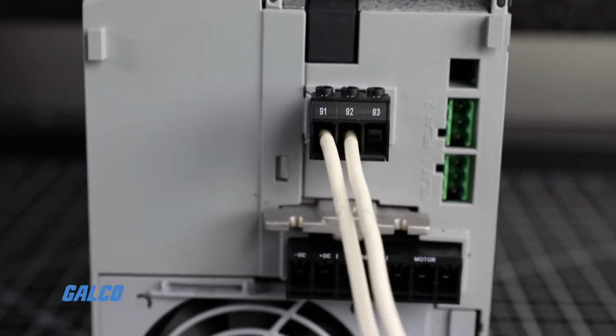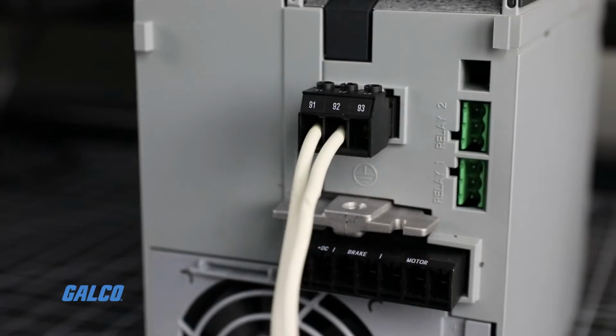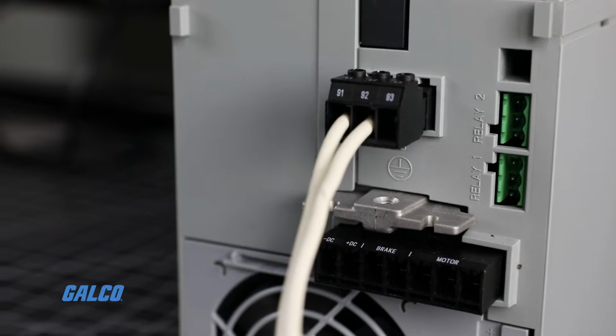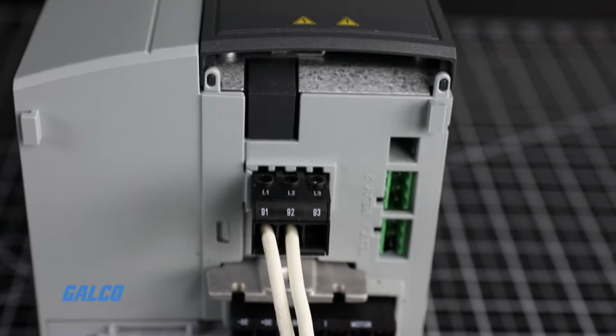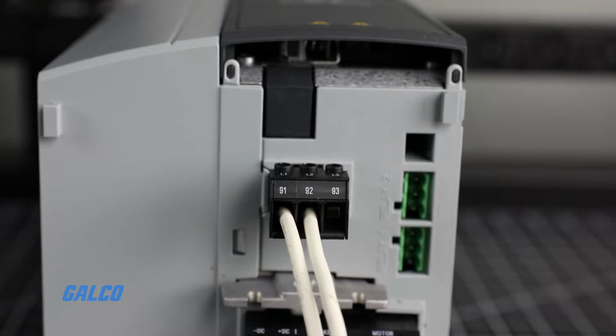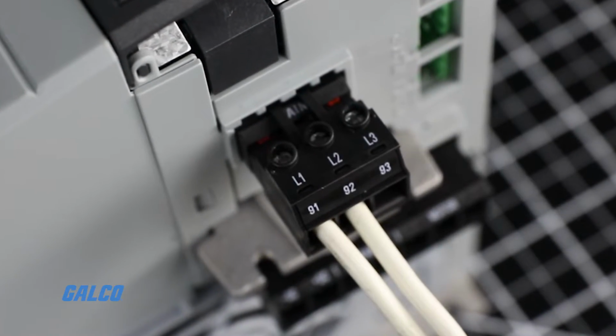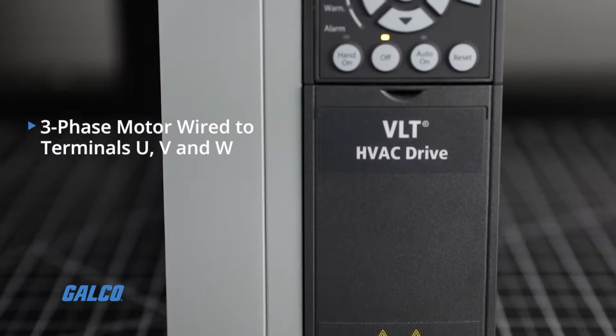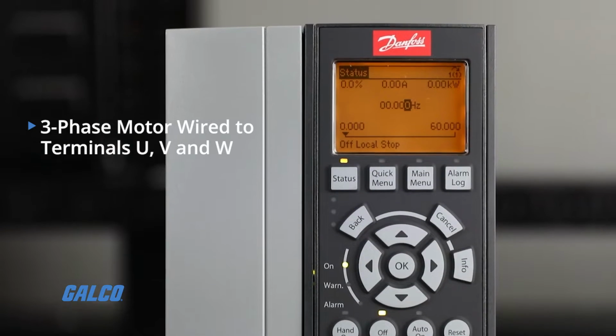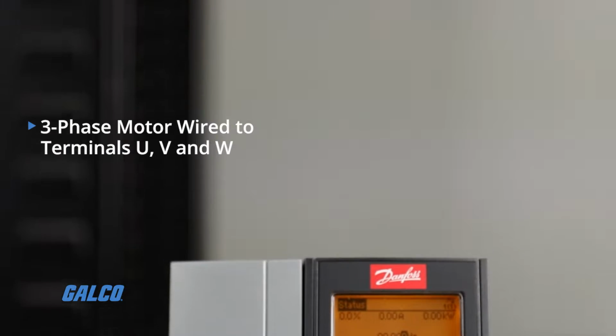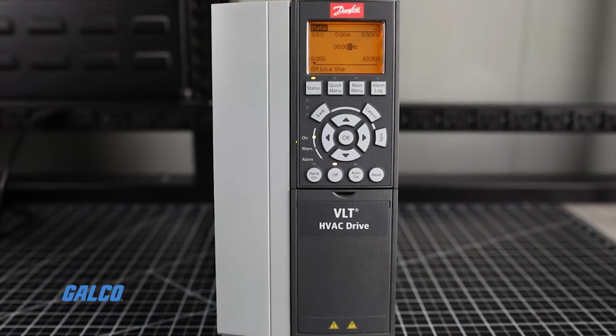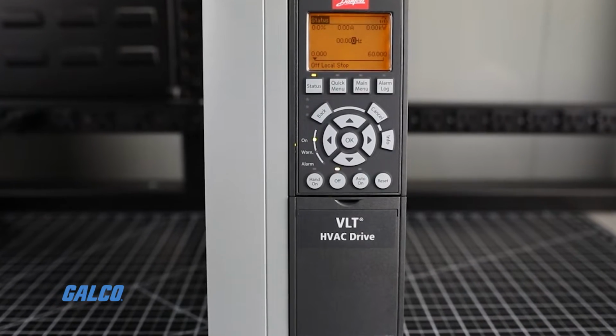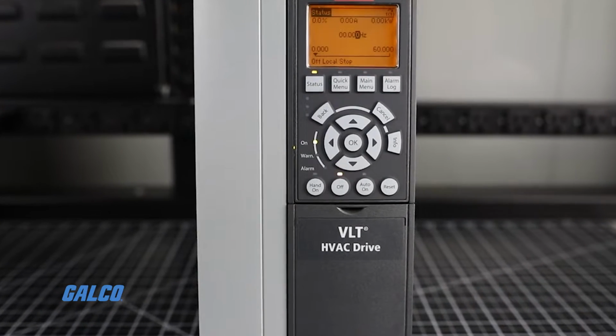Before you begin, make certain that your drive is properly installed and wired. Input power connects to terminals L1, L2, and L3. Your three-phase motor will be wired to terminals U, V, and W. By default, your speed reference will be wired at terminal 53 for analog input.